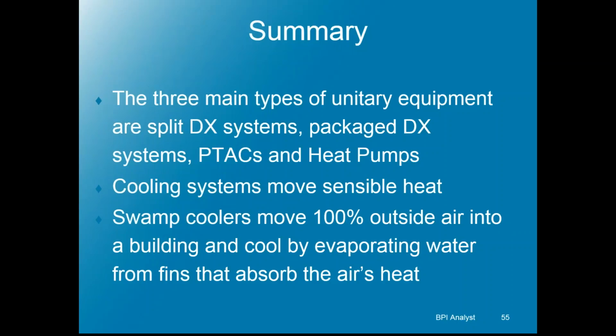So the three main types of unitary refrigerant-based systems are going to be a split DX, DX is direct expansion, a packaged DX, and then PTACs, and even PTACs have direct expansion valves in them. And cooling systems just move sensible heat, and then swamp coolers are typically 100% outside air, and they're very efficient.